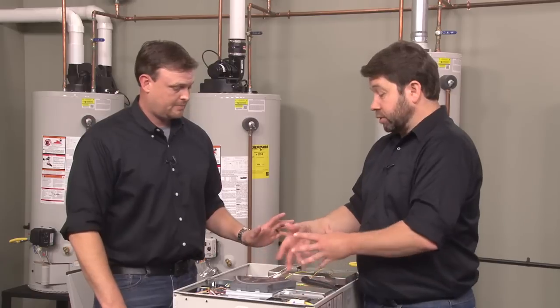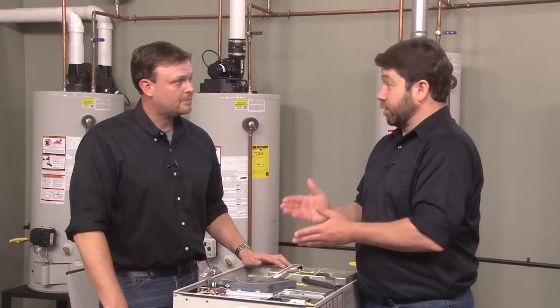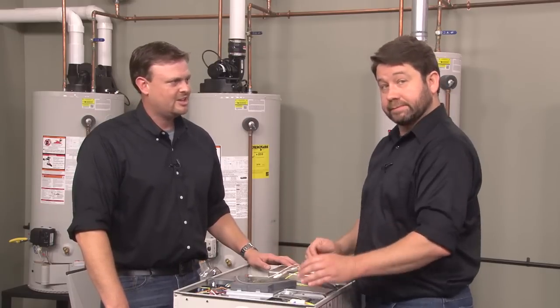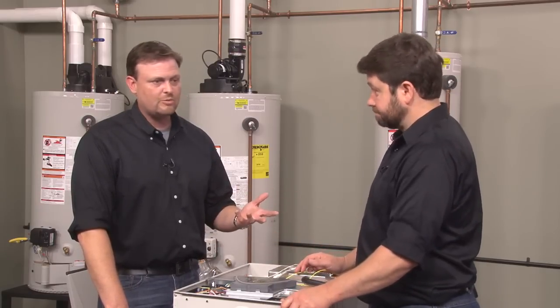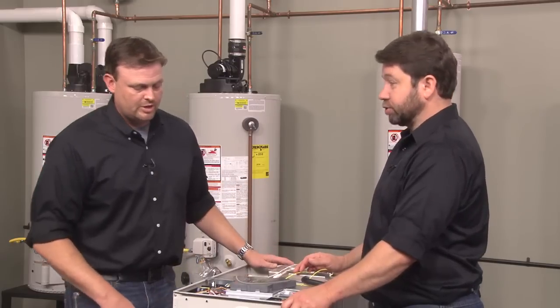We tell you to take it up to 140 because that's a temperature we know it's going to happen, but it's actually about 130 degrees when that bypass will close. At 140 we know it's going to close for sure, so we let it run for a couple minutes just ensuring that it did close. Then you unplug it.